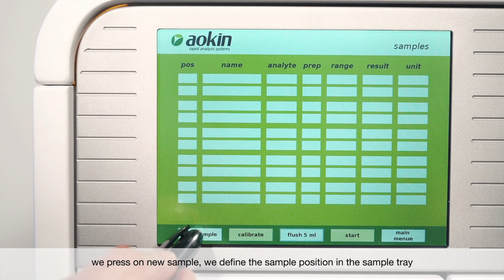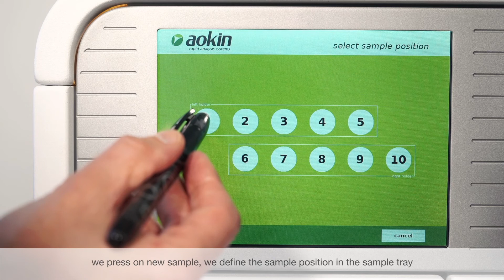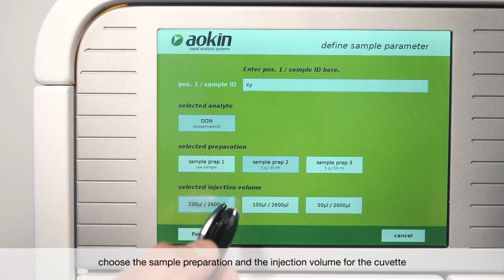We choose again the analyte. We don't need a calibrant. We press on new sample. We define the sample position in the sample tray. Enter the sample ID. Choose the sample preparation and the injection volume for the cuvette.